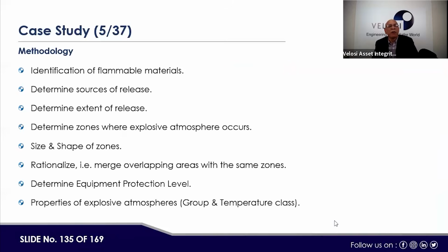This is the plant, and this is the sea and jetty where the ships are coming for the loading. Methodology: identification of flammable materials, determine source of release, determine extent of release, determine zone where explosive atmosphere occurs, size and shape of zones, rationalize and merge overlapping areas with the same zone, determine the equipment protection level, properties of explosive atmosphere group and temperature class.